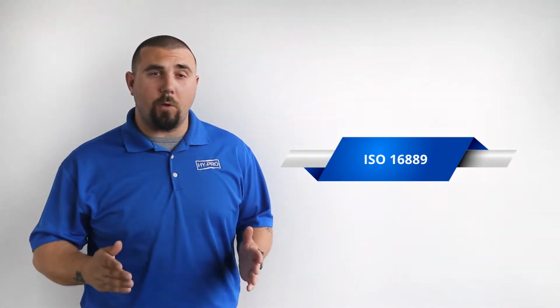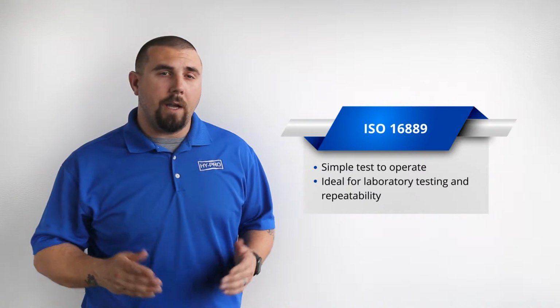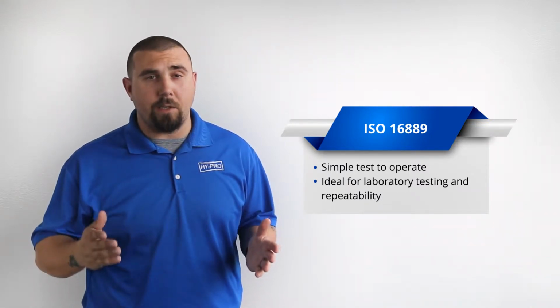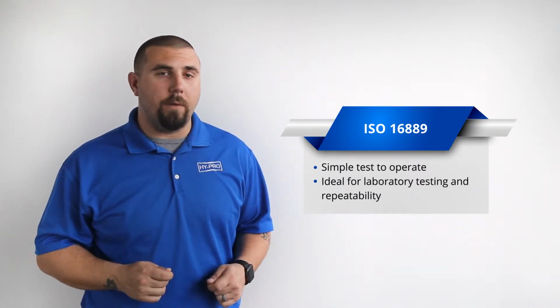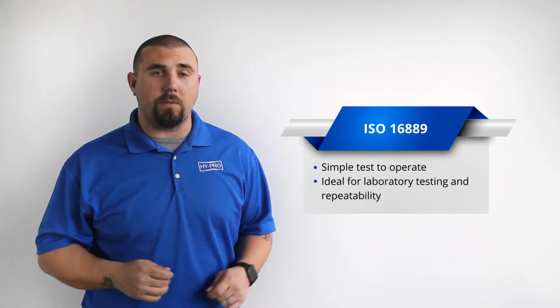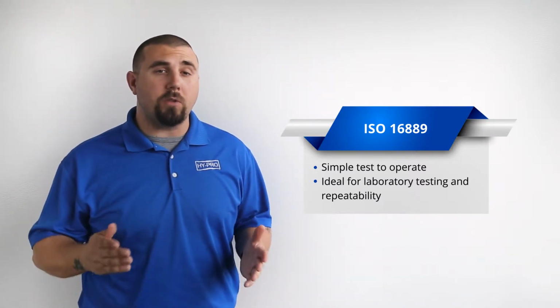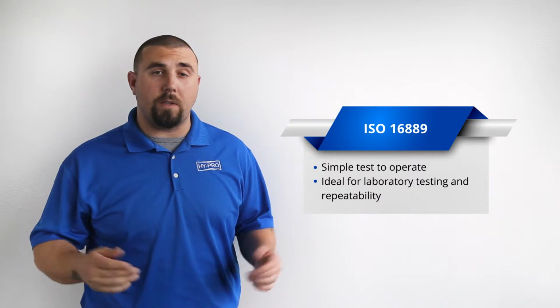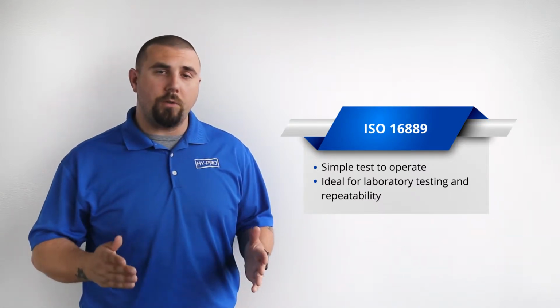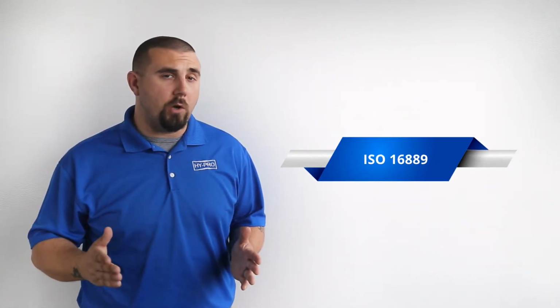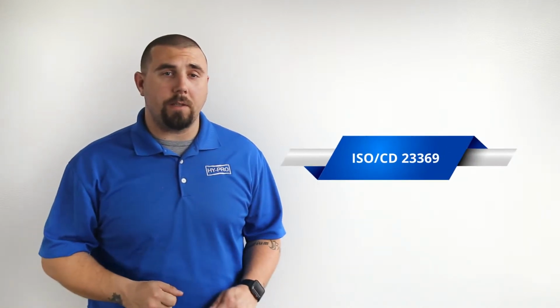Some important things to know about ISO 16889. It is the simplest test to operate and is ideal for laboratory testing and repeatability. Because of this, the test is the furthest from being a real-world example of how most hydraulic and lubrication filters interact with contamination. Also, due to its steady flow rate, the test offers no view on how flow rate fluctuation can impact filter performance.